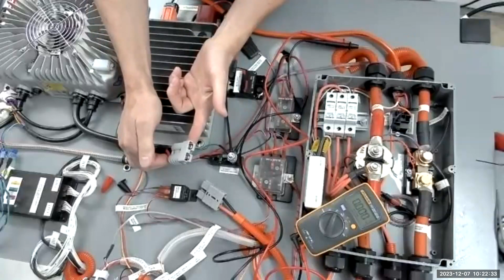In this case, I've disconnected the charger, and then I would perform the same test: go from my high voltage, check it, watch it fall; go to the ground, check it, watch it fall. So whenever you found the component that was causing the leak, then the voltage would drop.